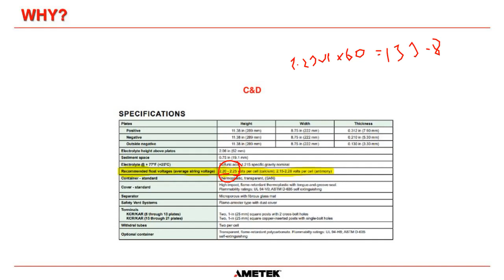But in normal operation, as long as your cells are within the boundaries of what the battery manufacturer says, then you do not need to do an equalized charge. So when you say our batteries are only ever used once every 5 years during a load test, that's fine, Clint. You don't have to equalize them unless it goes out with that spread.